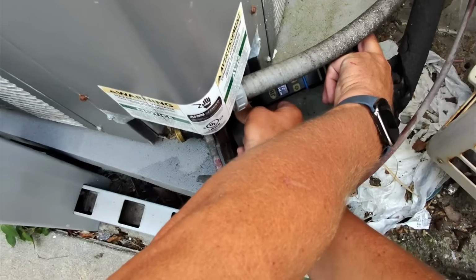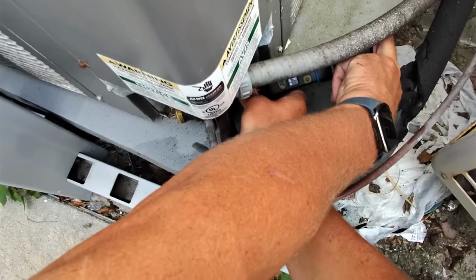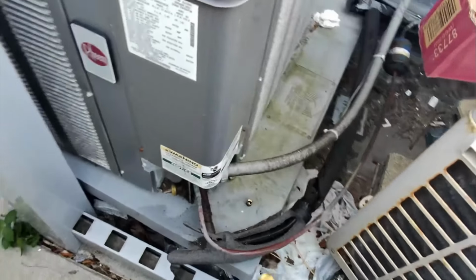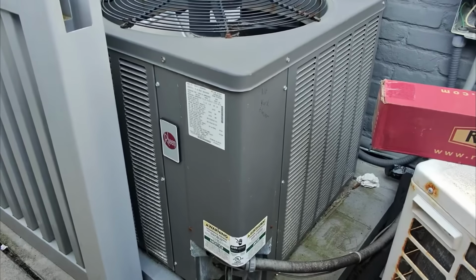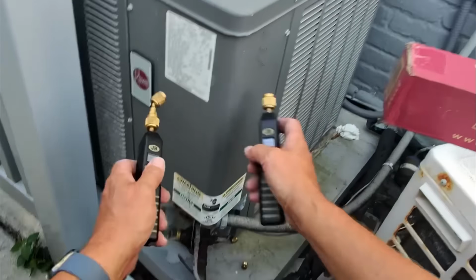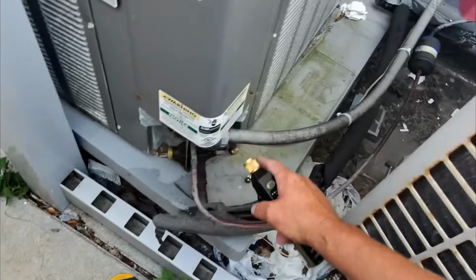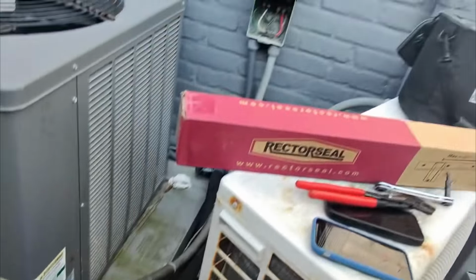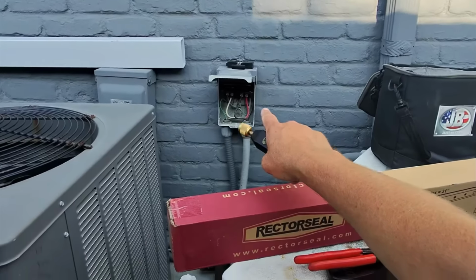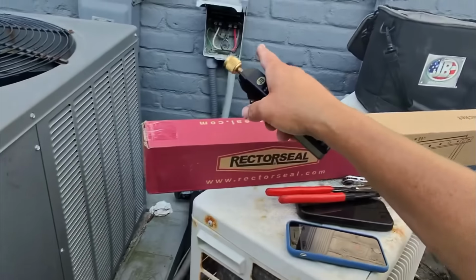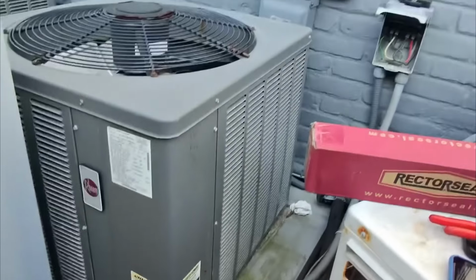So it's awesome that we're able to pump down the system into the condensing unit. Let's remove the access panel with a 1/4 inch driver, disconnect the electric. We're gonna just make sure there's no power going to our whip. I'm using a multimeter, and then we'll start cutting this out.